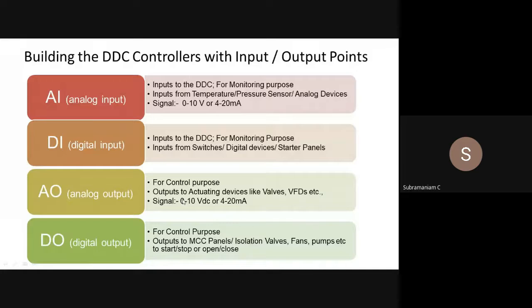Analog output is if I want to control a valve or if I want to control the VFD speed or something like that. Then the controller will give an output to that VFD: you run at 40 hertz or 35 hertz or something like that. It will instruct. That means it is an analog output. If I give an instruction to a compressor or a fan or a pump to start or stop, that means either it is on or off. That means that is a digital output that my controller is giving. So this is how your controllers are built with these four terminologies, which is analog and digital.